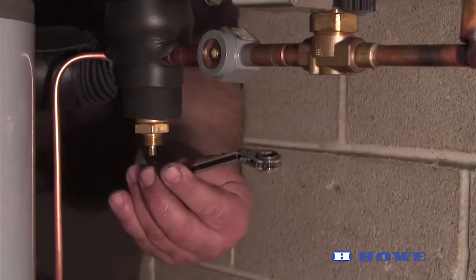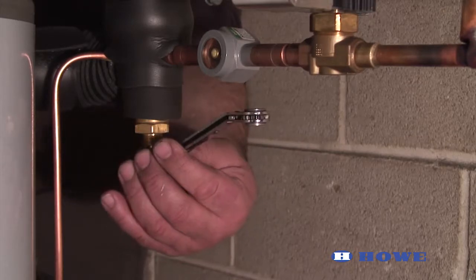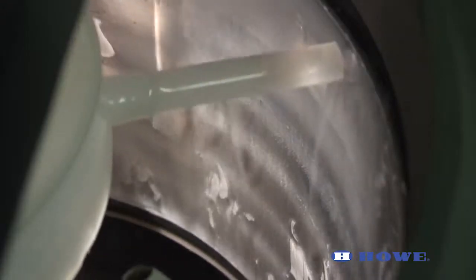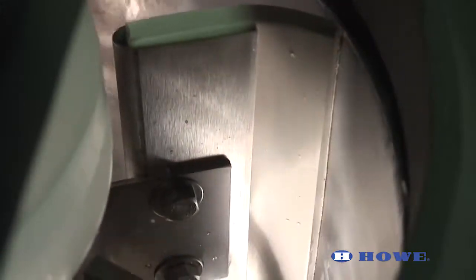If the expansion valve is open too far, liquid may flood back to the accumulator on your refrigeration rack or condensing unit. If this is happening, close the expansion valve a quarter turn at a time until you see ice being left on the lower section of the evaporator.